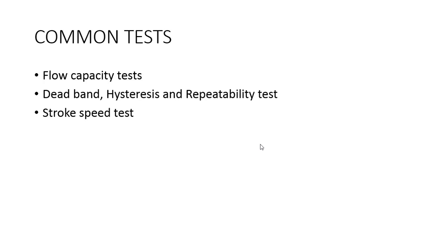Next are the common tests which are used in the control valve. These tests are not performed on all valves and are only requested by the customer. First is the flow capacity test. This is to determine the maximum flow through the valve and also the flow characteristic based on the valve opening.